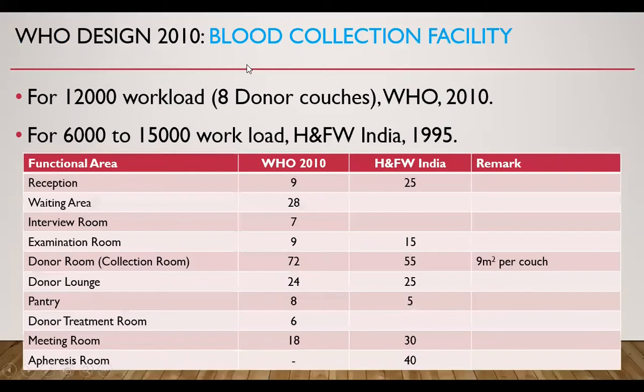The functional areas of Blood Collection Facility — these requirements are for a workload of 12,000 units per year requiring 8 donor couches (WHO 2010), and for a workload of 6,000 to 15,000 donations per year (Health and Family Welfare India 1995). The Blood Collection Facility includes a reception area, waiting area, interview room, examination room, donor room (actual collection room), donor lounge, pantry, donor treatment room (in case of any adverse reaction), and meeting room. These figures are in square meters and represent area requirements from both guidelines.